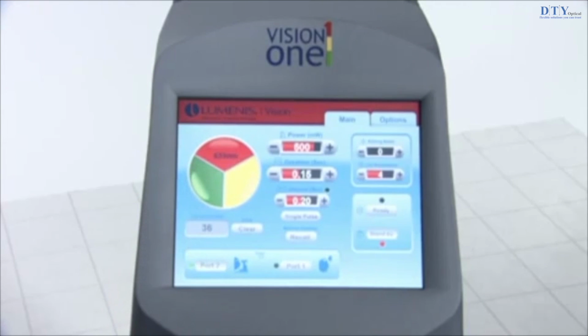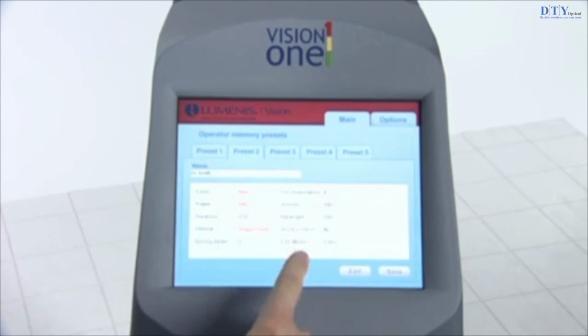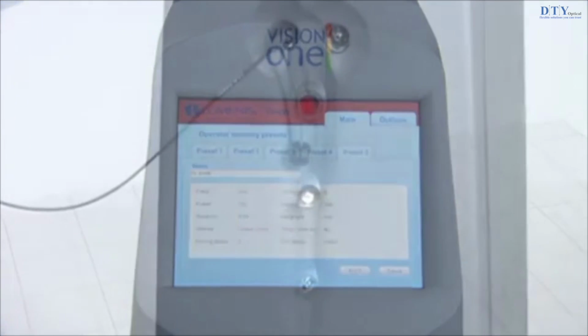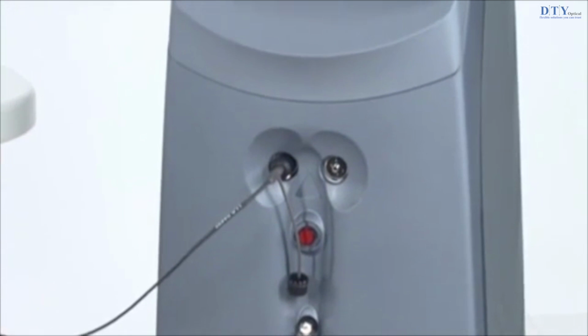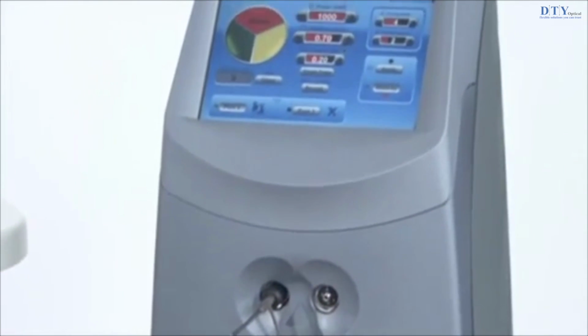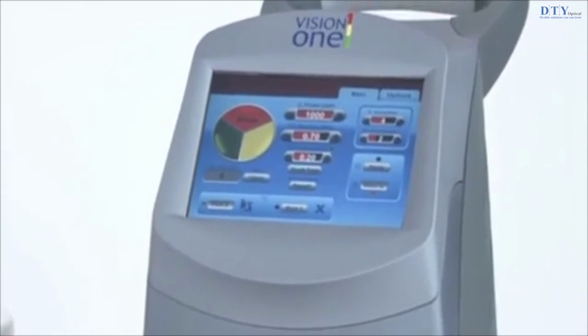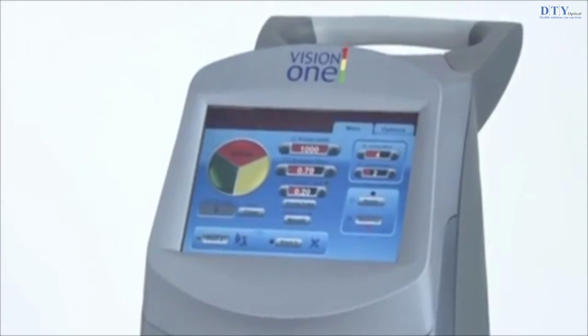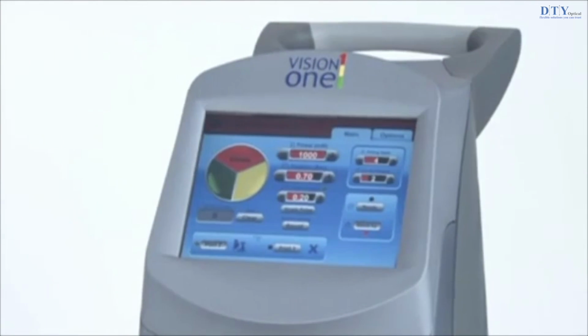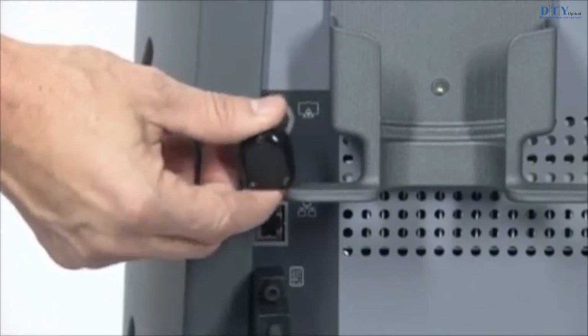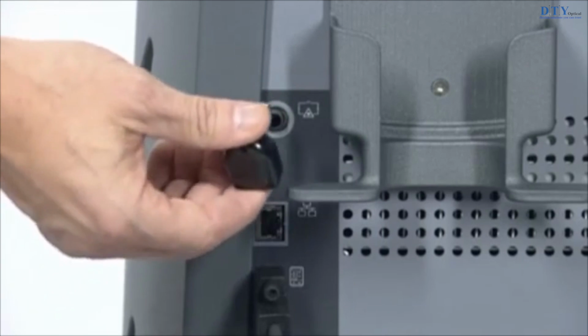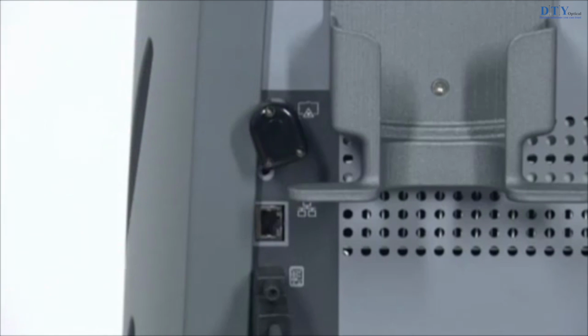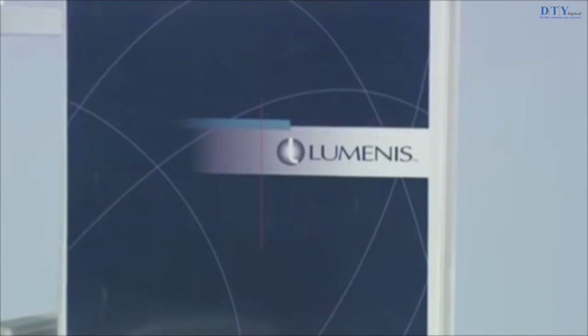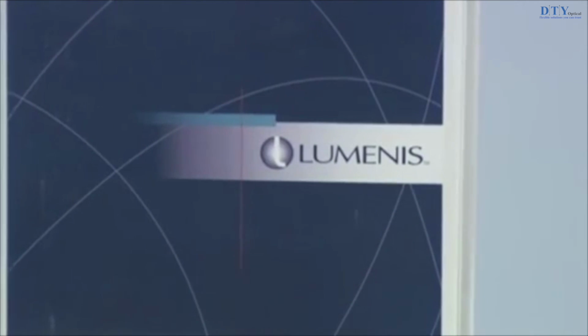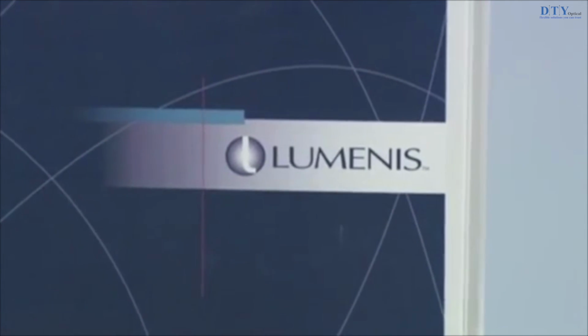Operation and adjustment controls are located so that the user need not be exposed to laser radiation during the laser operation or adjustment. The laser has a protective housing that prevents unintended human access to laser radiation above Class 1 limits. The housing must only be opened by a Lumenis certified technician. An external door interlock receptacle and plug are provided to disable the laser if the treatment room doors are opened. Refer to the Laser Safety Eyewear section of your operator's manual for additional information.